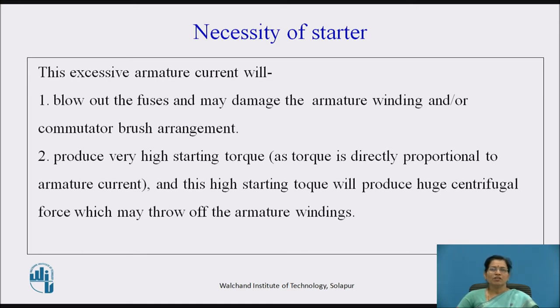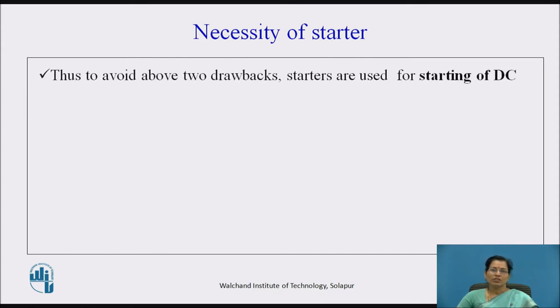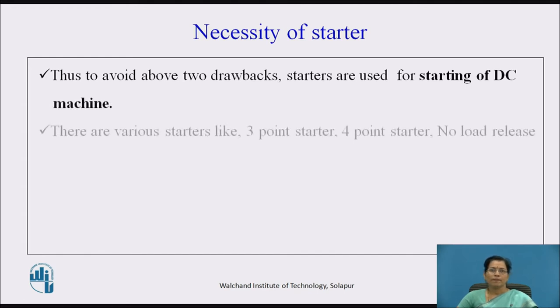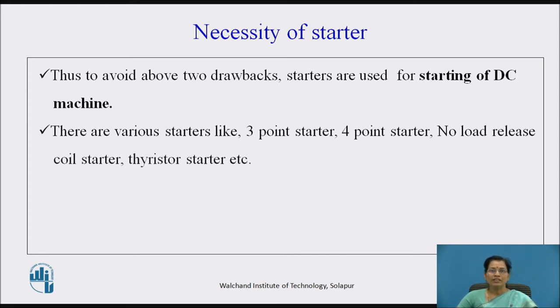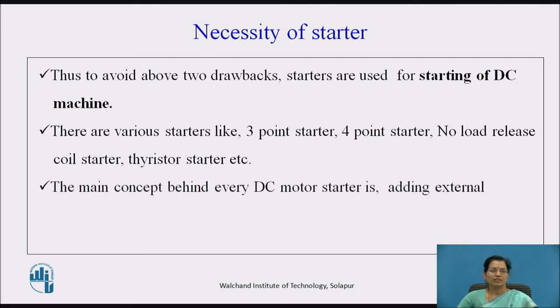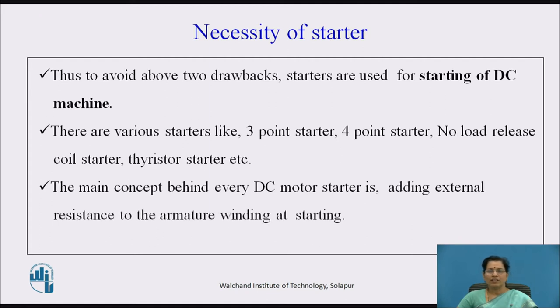High starting current produces very high starting torque, as torque is directly proportional to armature current, and this high starting torque will produce a huge centrifugal force which may throw off the armature winding. So starters avoid these two drawbacks and are used for starting of DC machines. There are various starters like 3-point starter, 4-point starter, no-load release coil starters, thyristor starters, etc. The main concept behind every DC motor starter is adding external resistance to the armature winding at starting.